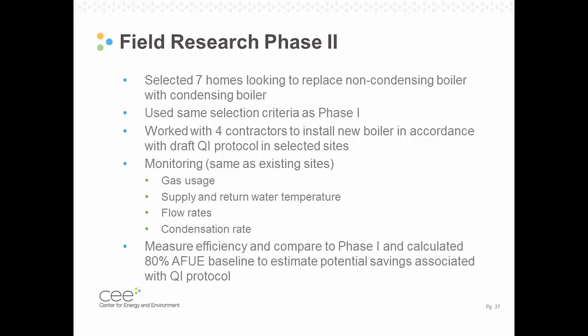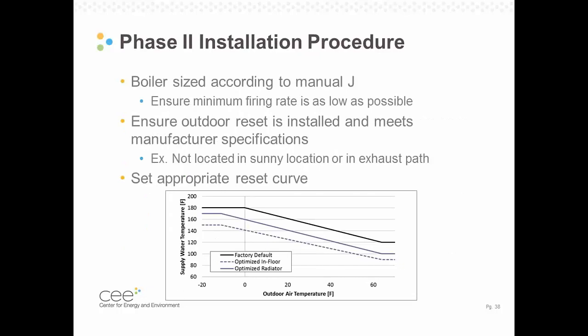So that being said, we moved on to phase 2, which was new installs. So we were looking to replace non-condensing boilers with brand new boilers using a QI install phase that we developed based on those last protocols, and then monitor that and compare the data backwards. So really the biggest points of this QI protocol are to size the boiler appropriately, ensuring that it does have modulation, which allows the outdoor reset to work and that ramp up control to work.